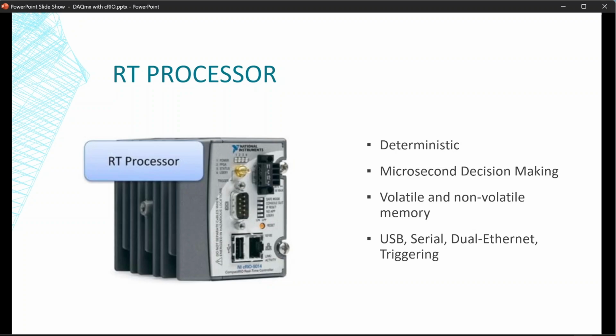So your RT processor. As I mentioned, the RT stands for real time, meaning that it's very deterministic. So much better than if you try to program something on a Windows computer and you tell it, hey, do something every 5 milliseconds, you're really 5 milliseconds plus or minus a good chunk, and it may not even be consistent, right? You may have periods of time where you're 5 milliseconds plus or minus a couple microseconds, and then all of a sudden, Windows could decide to do a security scan and it could totally change everything. So these give you good reliability in terms of timing and in terms of jitter. It allows for microsecond decision making, so you can make decisions very quickly. If you build a control system into this, it can be very responsive. It has volatile and non-volatile memory, and these allow for USB devices, serial, dual Ethernet, triggering, etc.